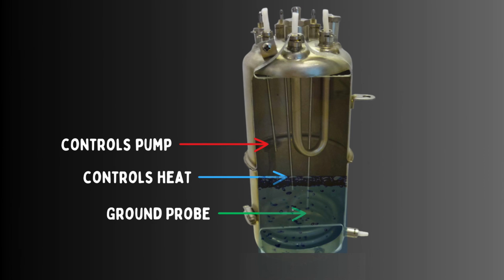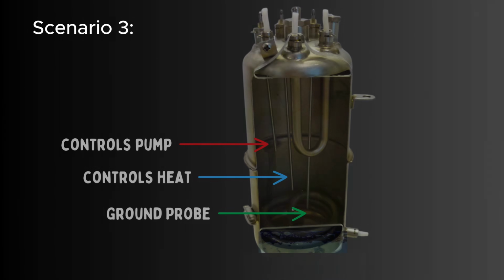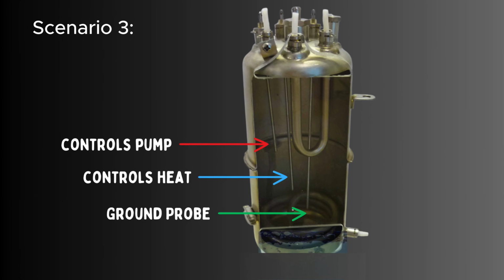And then finally number 3, the element comes on and the boiler is bone dry. This is the worst case scenario. And this can happen if both those probes are playing up. And if you're lucky, the thermal fuse will blow, but quite often the element gets so hot so quickly that it burns through its own insulation, and essentially you've got to go out and buy a whole new boiler.